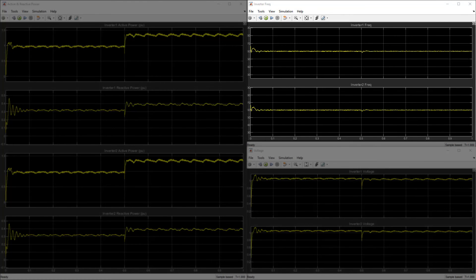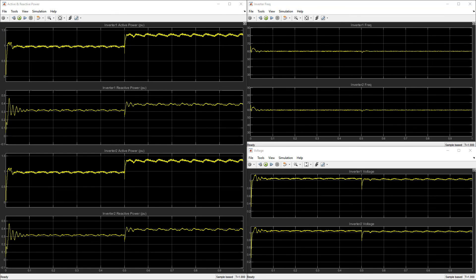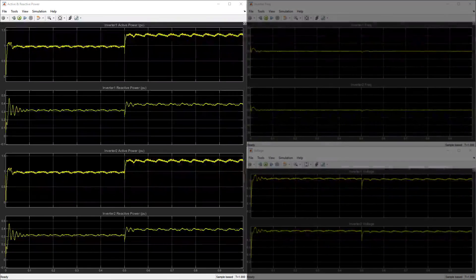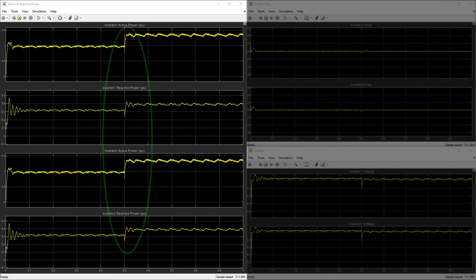Likewise, the microgrid frequency is also maintained at 60 hertz. Looking at the active and reactive power scopes, we see that the real and reactive power loads are shared between both sources without any high-level supervisory control.